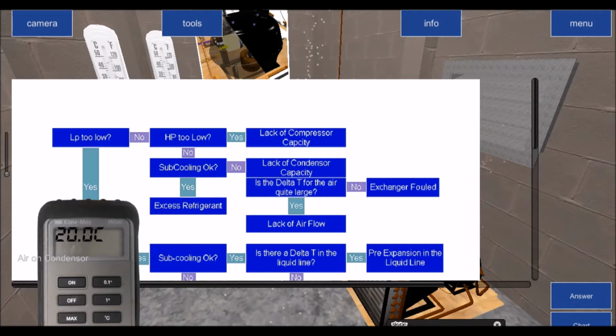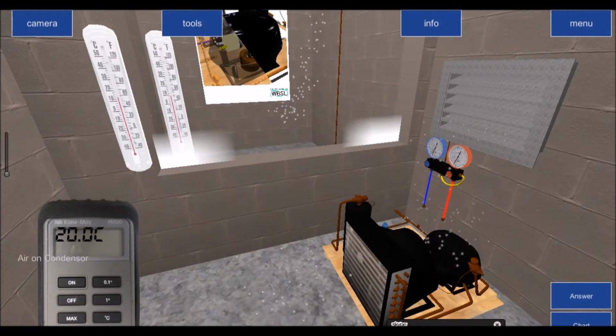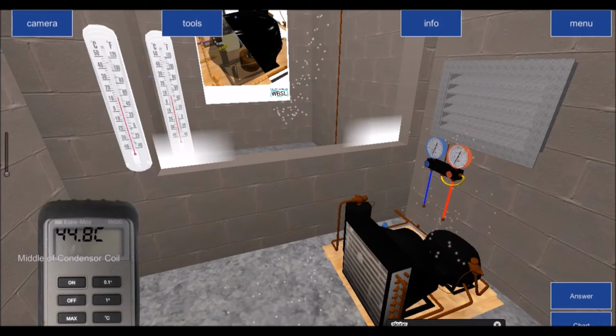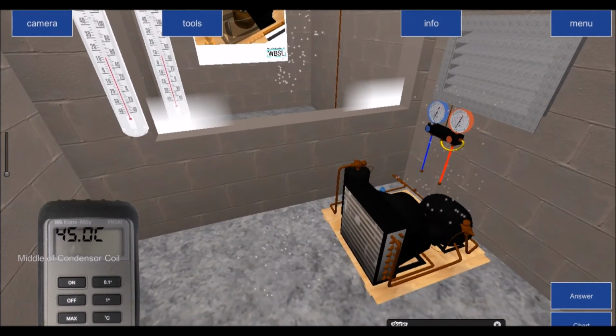Next question is, is subcooling okay? Subcooling is the difference between the condensing temperature, which in this case is 45 degrees, and the liquid temperature as it leaves the bottom of the condenser. So this little pipe here at the outlet of the condenser, that's 42 degrees. So is subcooling okay? That's 3 degrees of a difference. Subcooling should be between 4 and 7 degrees of difference. So subcooling is not okay, because normal or good subcooling should be a minimum of 4 degrees and anything above that. It works between 4 and 7, but if you had 8, 9, 10, then you would be saying your subcooling is excessive. If anything, it's excessive. But in this particular case, subcooling is lower than normal.